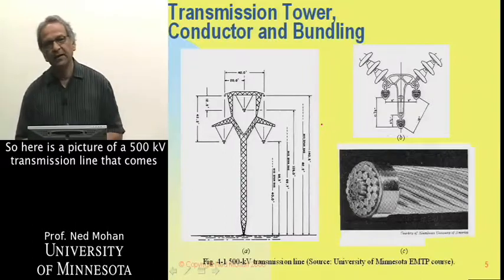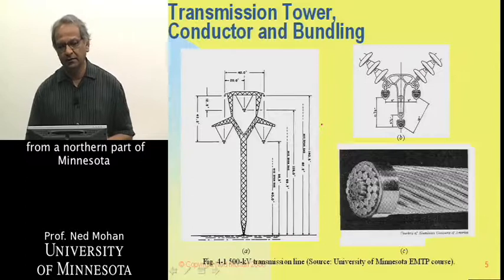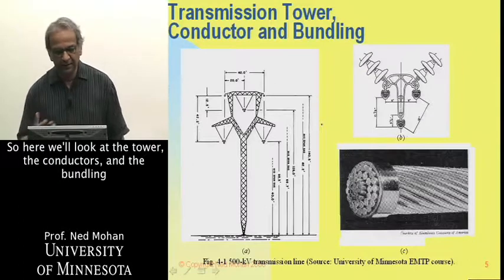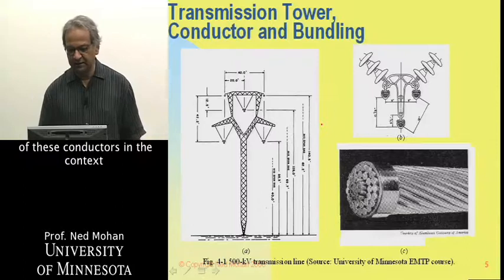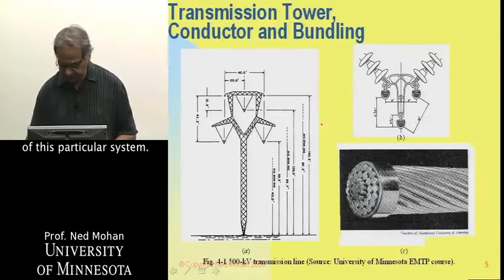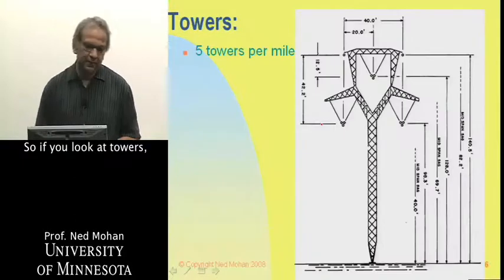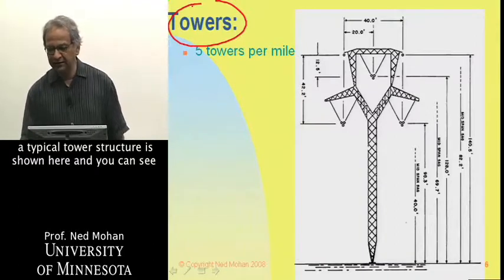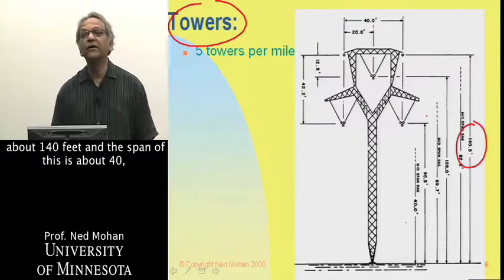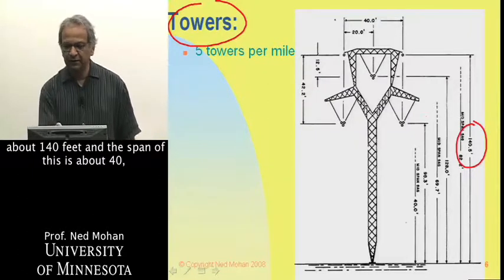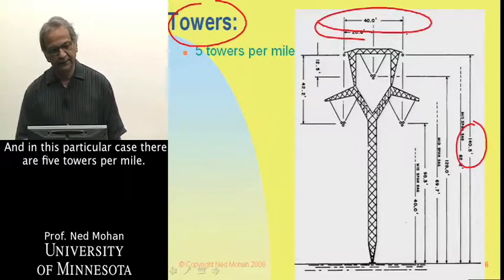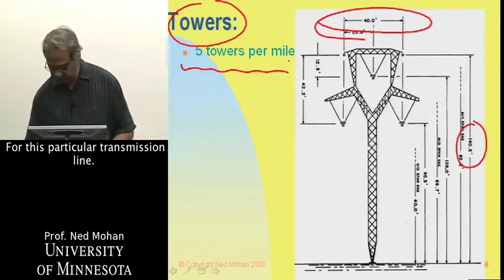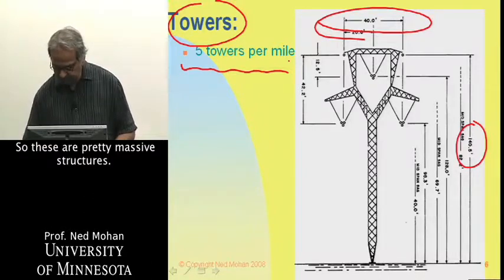Here is a picture of a 500 kV transmission line that comes from the northern part of Minnesota to somewhere very close to the Twin Cities. Looking at the tower, the conductors, and the bundling of these conductors in context of this particular system: a typical tower structure has a height above ground of about 140 feet, a span of about 40–50 feet, and in this particular case there are five towers per mile. These are pretty massive structures.